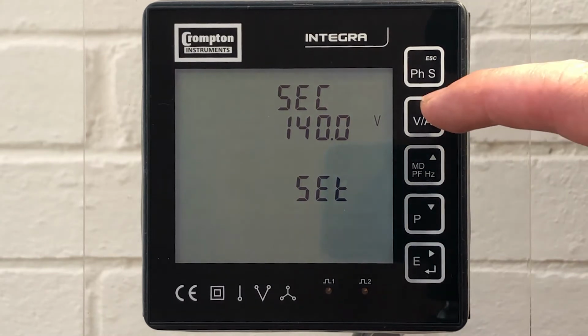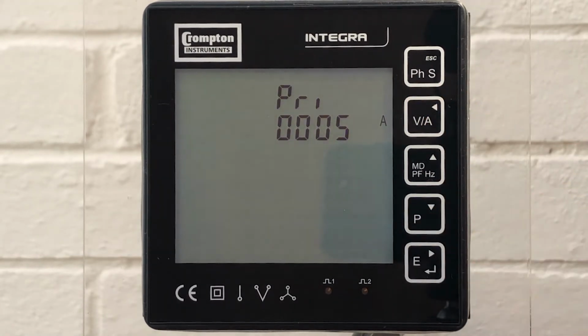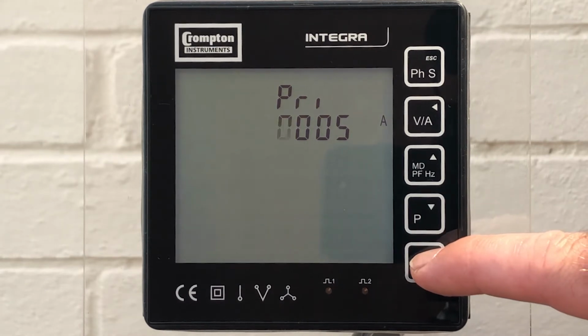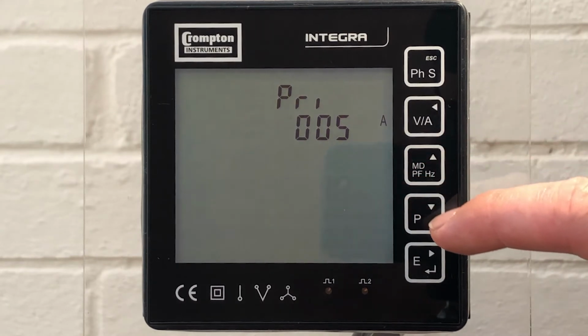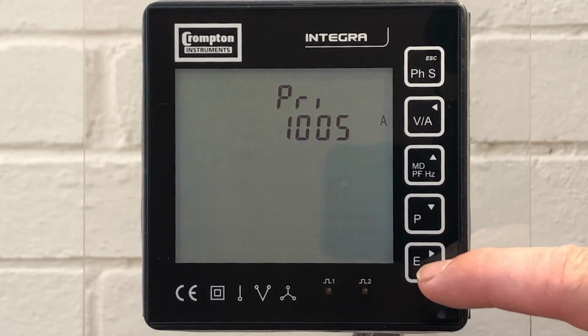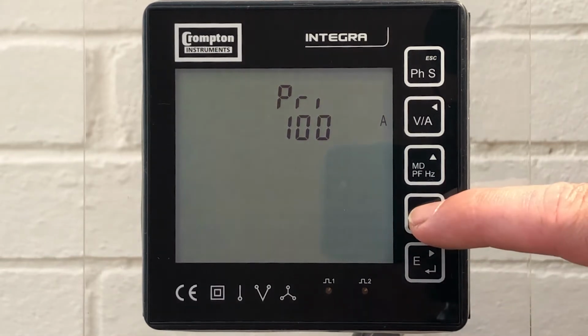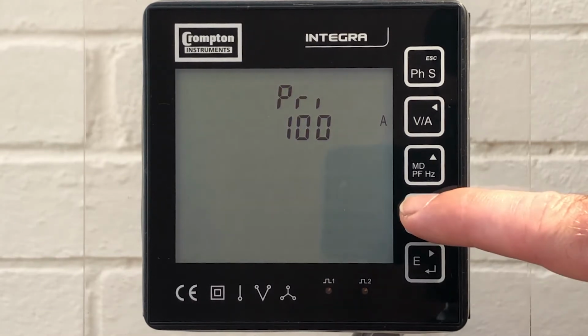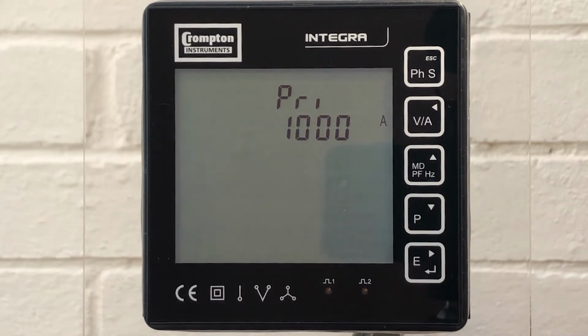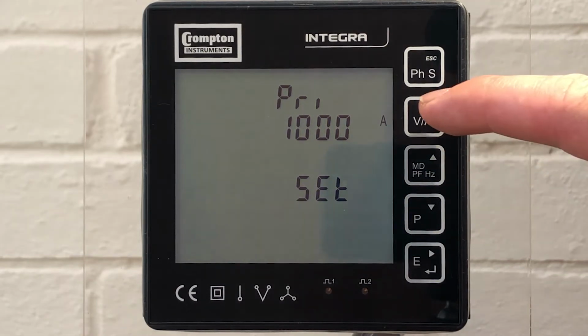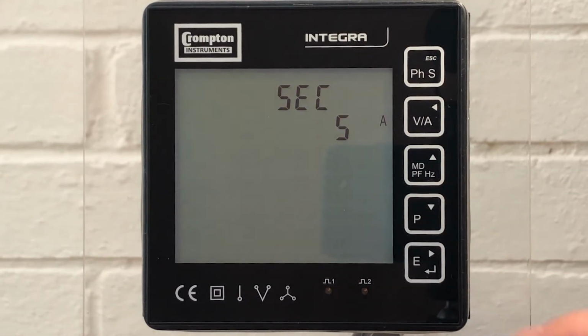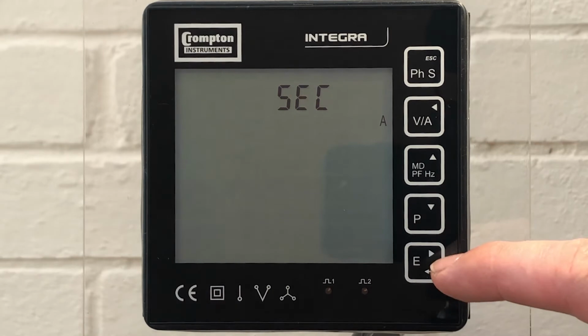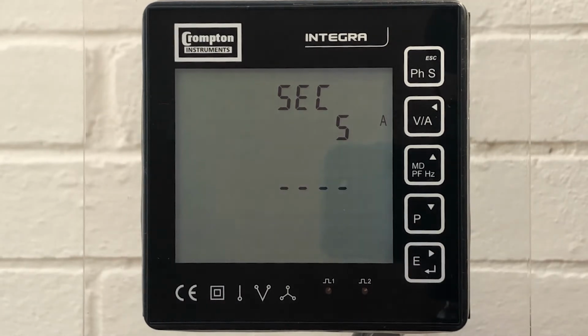Now we've set our voltage transformer ratio, press VA to escape this screen and arrow down to the primary current. This is where we set the maximum primary current that can be monitored according to the CT in use. In this example, I'm going to set our primary CT to 1000 amps. And just hold E to set the primary at 1000. Now to set the secondary of the CT, you press the VA button, down to select the CT secondary, holding E. It's currently set to 5 amps and we can switch between 5 or 1 amps.